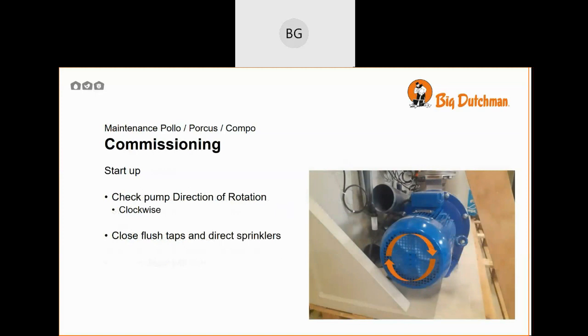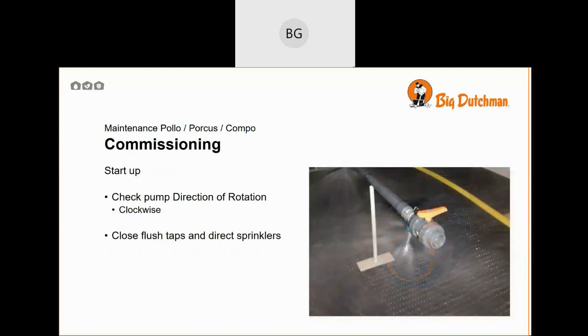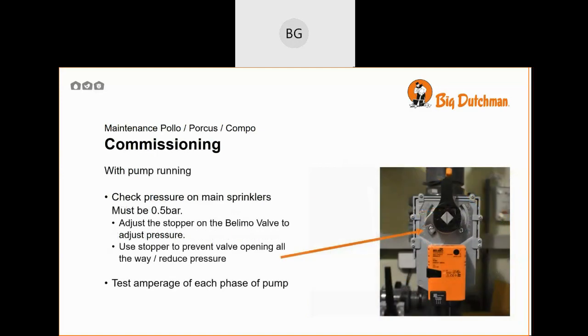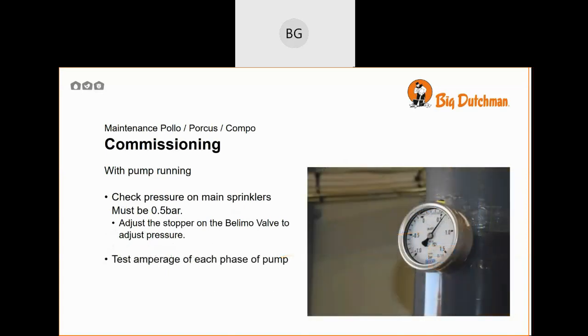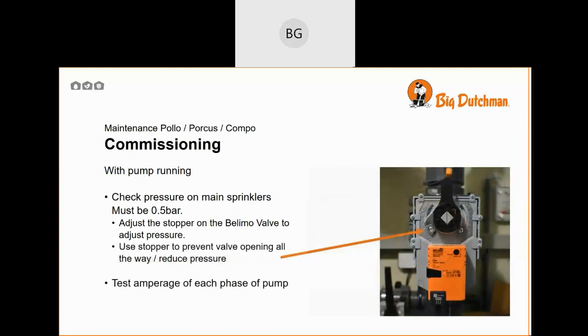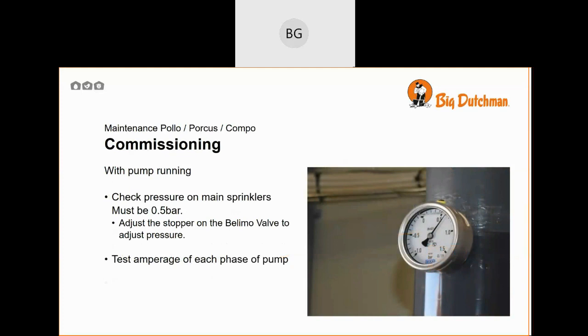Close all flushing taps at the end of the sprinkler lines. This will ensure that pressure builds up and the sprinklers function correctly. Check the pressure on the main sprinkler lines. Must be 0.5 bar. Adjust the stopper on the Belimo valve to adjust the pressure. Use the stopper to prevent the valve from opening all the way or reduce the pressure. You'll then need to test the amperage of each phase of the pump.